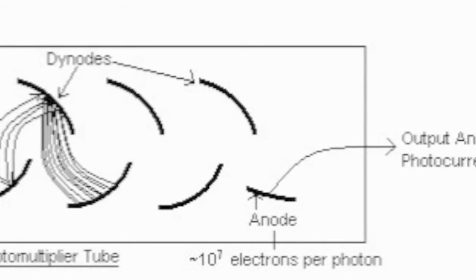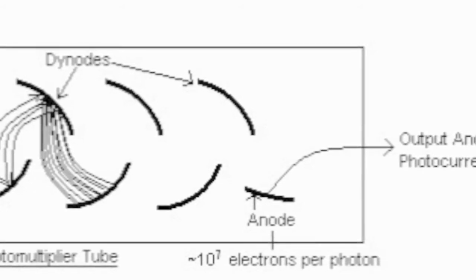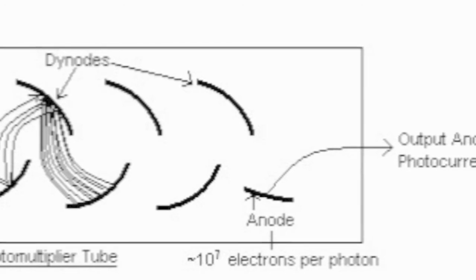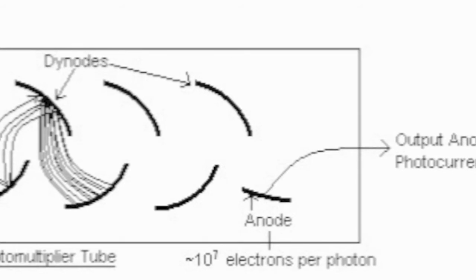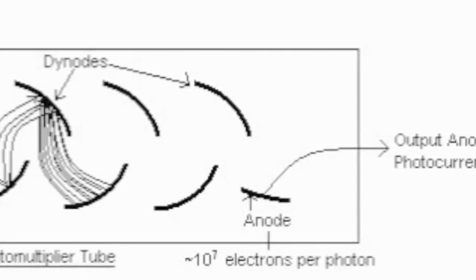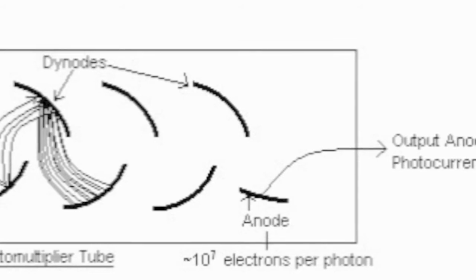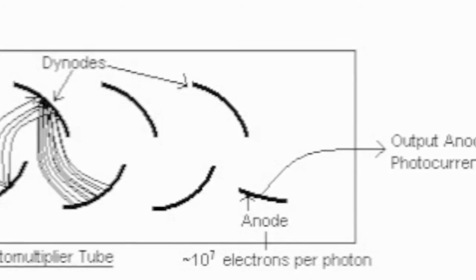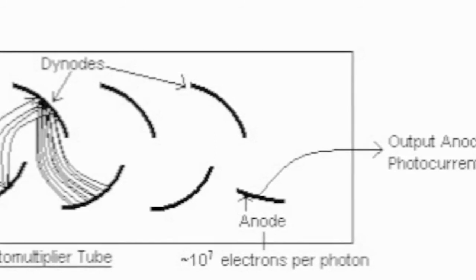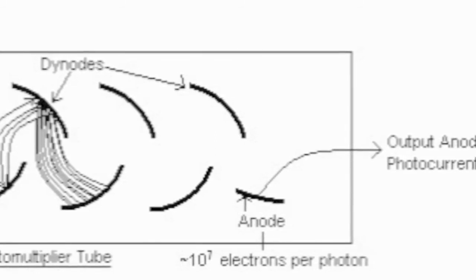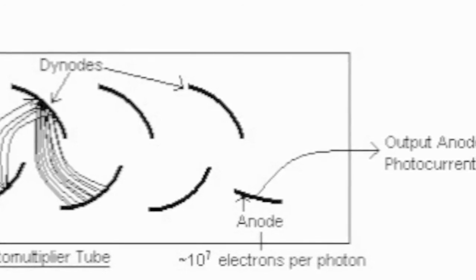That's why the higher amplification, the higher current, because the more amplification, the more electrons you will have flowing. And the higher the current, the higher the voltage because of V equals I times R. When the current goes up, so does the voltage. In this case, the resistance will stay constant all the time. So with the constant resistance and the current going up, the voltage will go up and it'll make my job easier later. That's how the photomultiplier tube works.